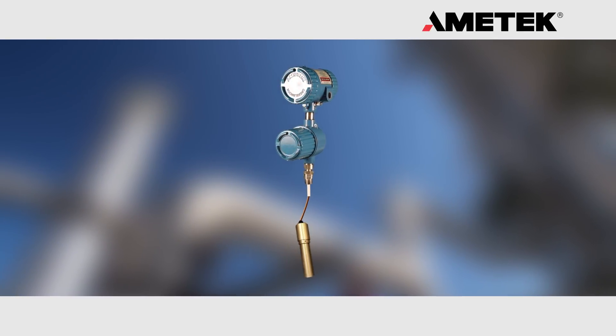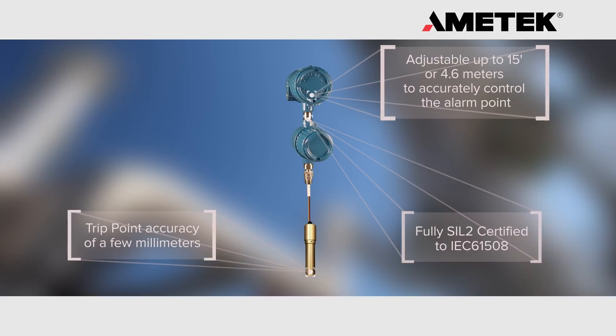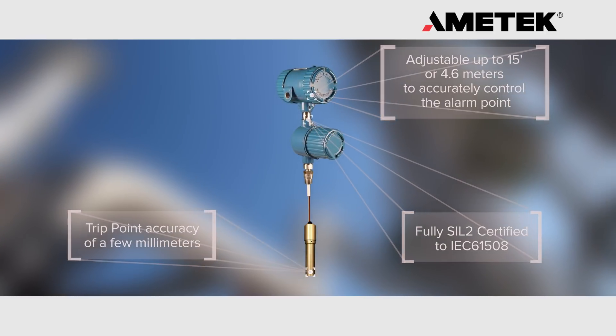Product features include adjustable up to 15 feet or 4.6 meters to accurately control the alarm point, a trip point accuracy of a few millimeters, fully SIL2 certified to IEC 61508.